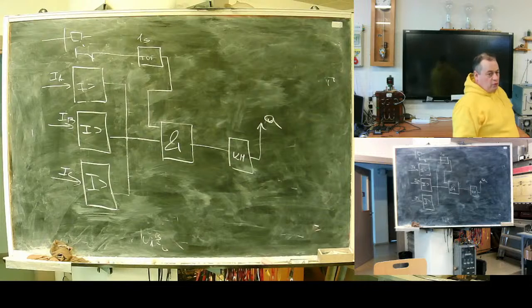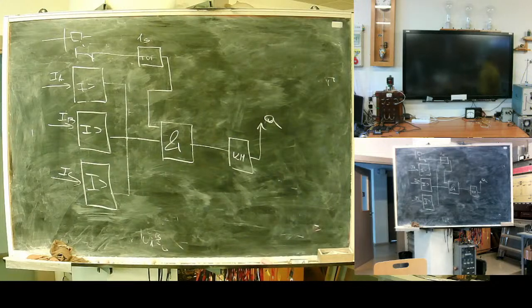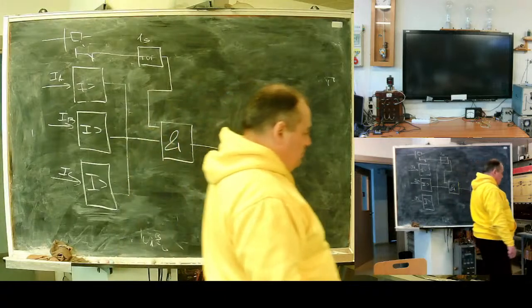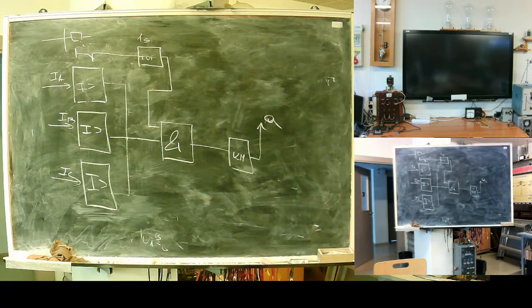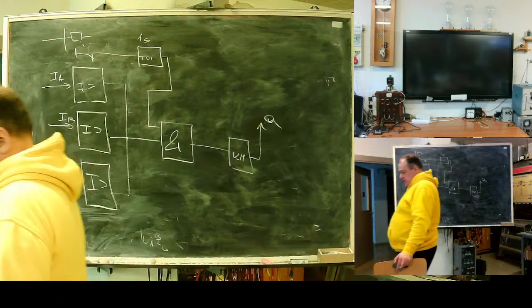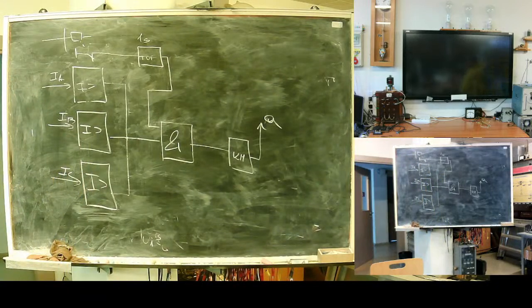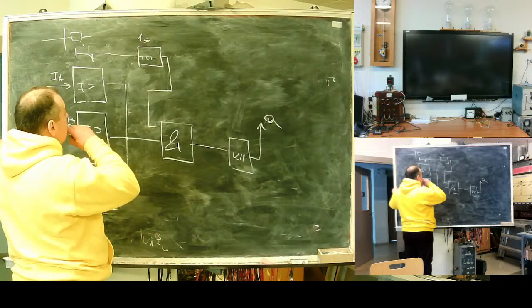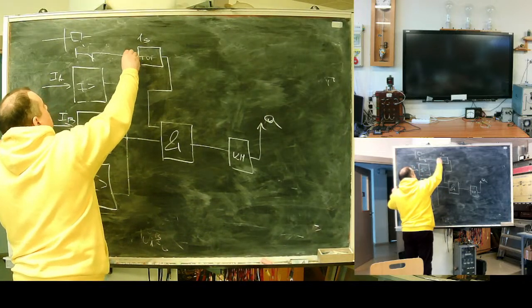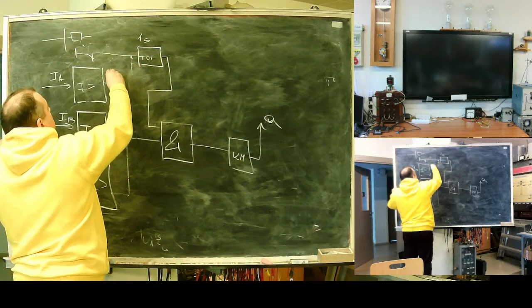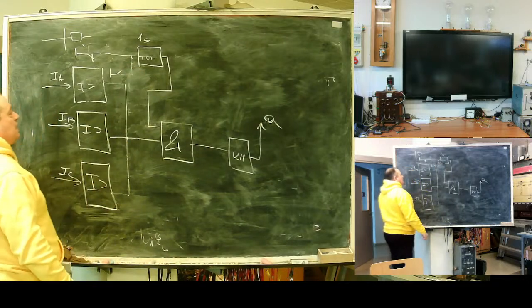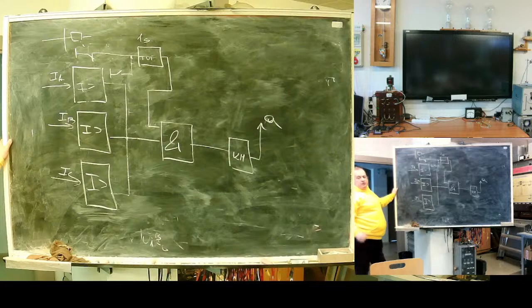Helps for switch on fault condition. This is for switch on fault. It activates only for a short time. It remains active for a short time after the circuit breaker is switched. There is another approach called speed up after. In speed up after, this circuit is activated by the make contact of the circuit breaker and start command. If you receive a switch on, not start but switch on command, this activates.